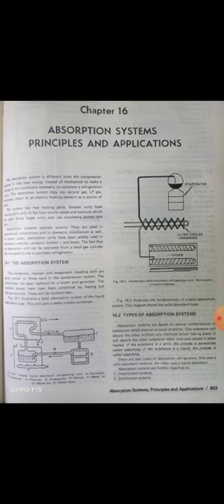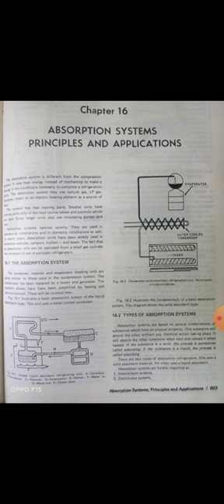Figure 16.2 covers types of absorption systems. Absorption systems are based on several combinations of substances that have a useful property: one substance will absorb the other without any chemical action taking place. It will absorb the other substance when cool and release it when heated. If the substance is a solid, the process is called adsorption; if the substance is a liquid, the process is called absorption. There are two types of absorption refrigerators — one uses a solid absorbing material, the other uses a liquid absorbing material.